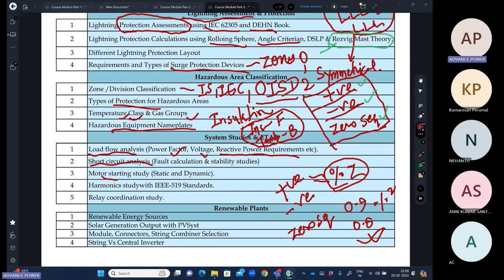We'll do the motor starting studies. We'll do the static analysis in which only starting current will be taken. We'll do the dynamic analysis in which the motor will be completely modeled, like it is connected with the pump, what is the starting time of the motors, and the motor characteristic we will model, and we'll see how it is affecting the voltage of the bus, and other motors which are also running. So we'll do the group starting of the motors also, and we'll see the voltage dip and the contingency analysis in that case. We'll do the harmonic study with IEEE 519 standards.